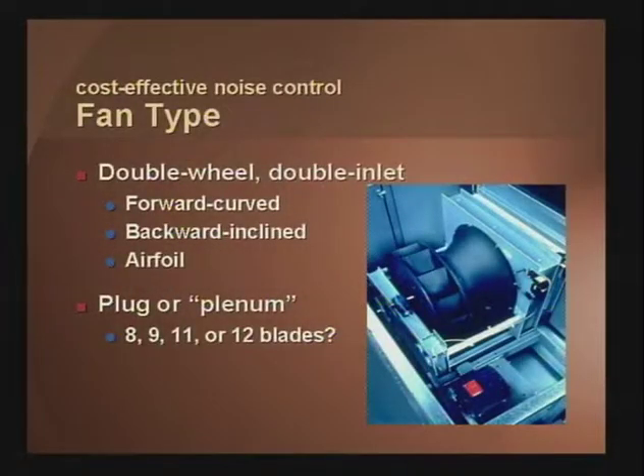Some of the fan types available to you in the higher end catalog products are basically five or six types. The basics are your double wheel, dual inlet, double wheel type fans, your forward curve, your BI, and your airfoil fans. BIs are good in lower frequencies if you have discharge plenums. Airfoils are quite good at higher CFMs.